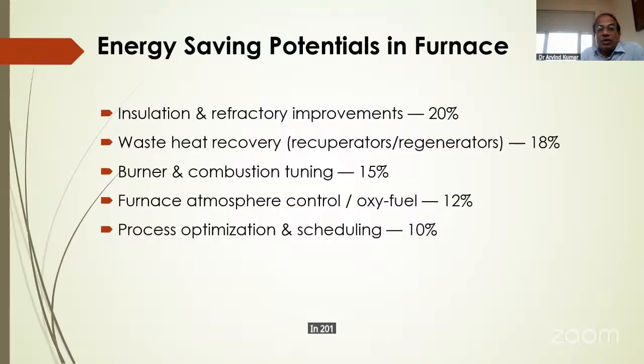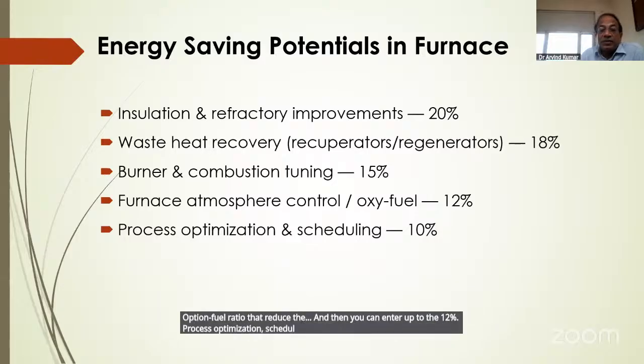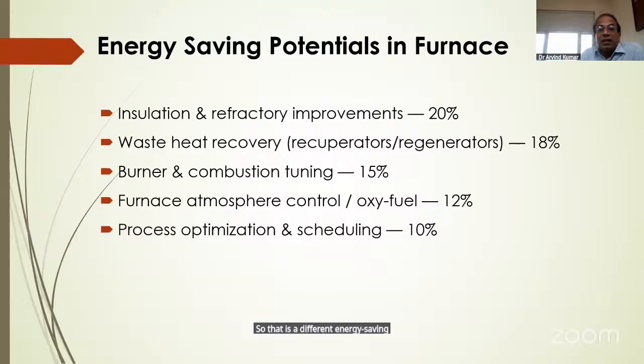Insulation and refractory improvements 20%, waste heat recovery with recuperators and regenerators 18%, burner and combustion tuning 15%, furnace atmosphere control, the oxygen-fuel ratio, which reduces energy consumption by up to 12%, process optimization and scheduling 10%. So those are the different energy saving potentials in a furnace, where the internal energy of the fuel is converted into heat energy, and heat energy into useful energy. In that transit, the energy losses have to be minimized.